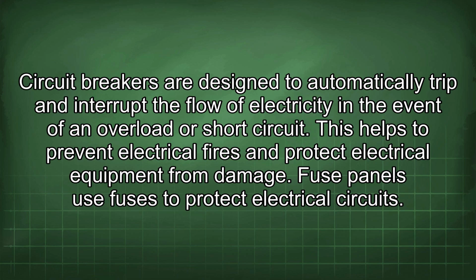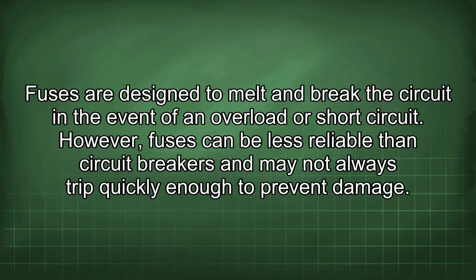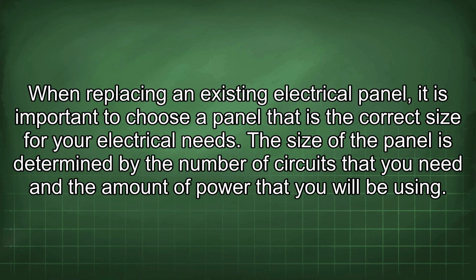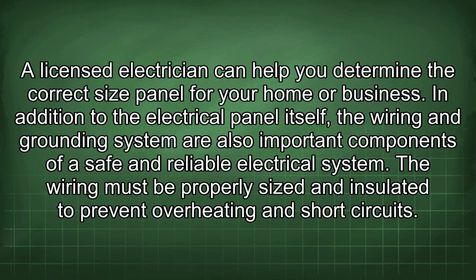Fuse panels use fuses to protect electrical circuits. Fuses are designed to melt and break the circuit in the event of an overload or short circuit. However, fuses can be less reliable than circuit breakers and may not always trip quickly enough to prevent damage. When replacing an existing electrical panel, it is important to choose a panel that is the correct size for your electrical needs. The size of the panel is determined by the number of circuits that you need and the amount of power that you will be using. A licensed electrician can help you determine the correct size panel for your home or business.